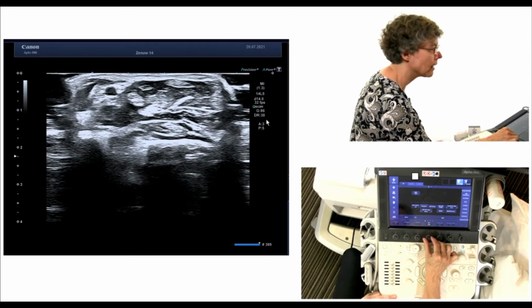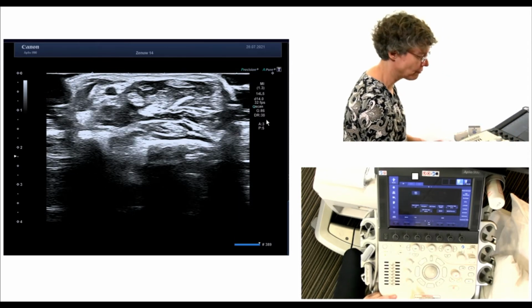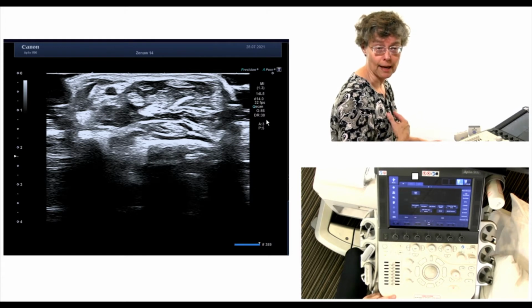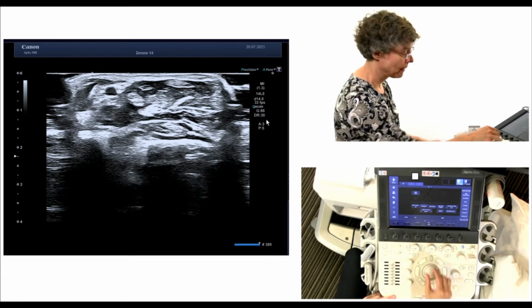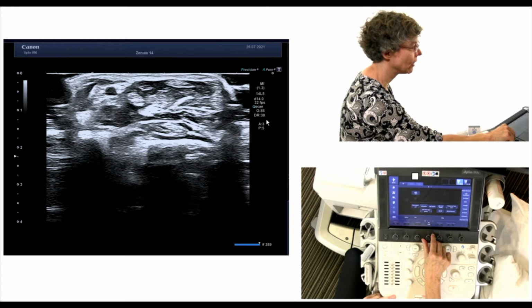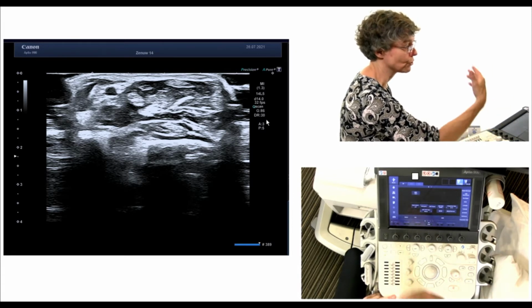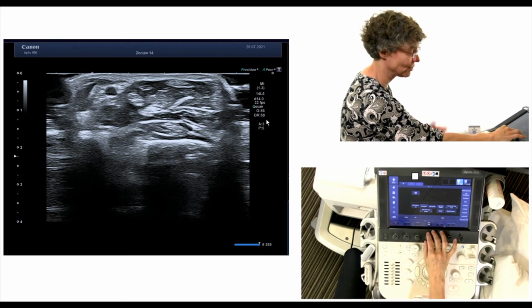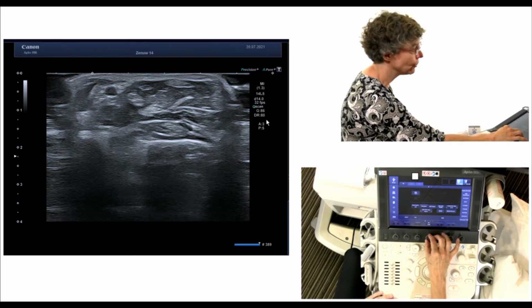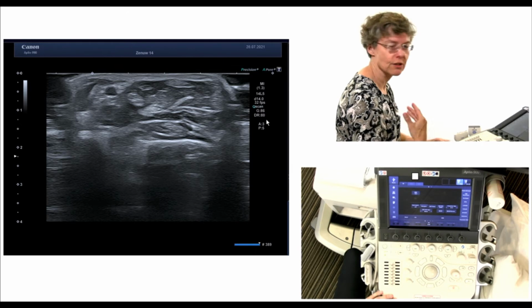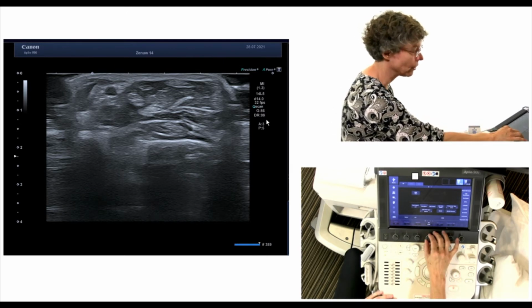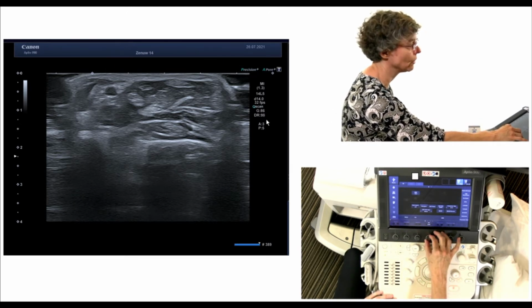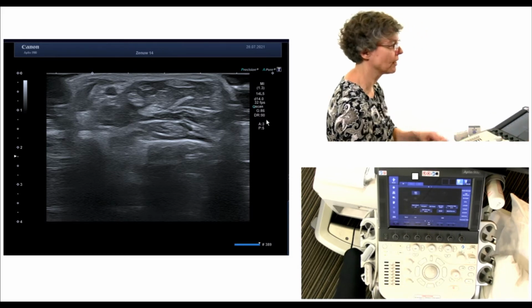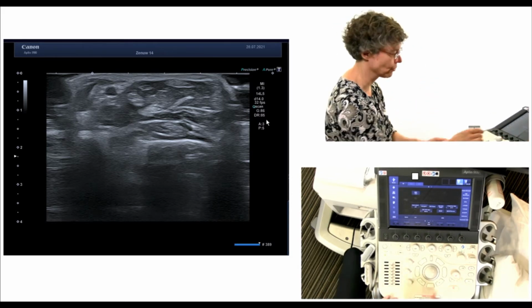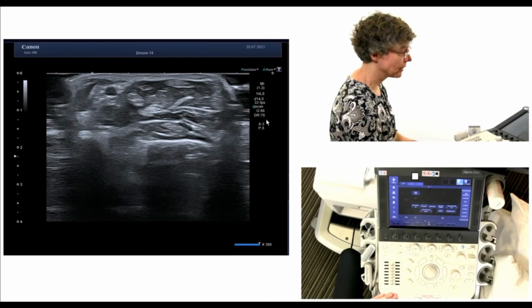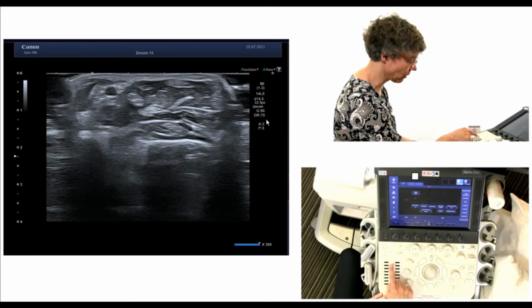And if we turn that down, the image becomes harder, right? So every pixel is sort of forced to choose between am I white or am I black? And if I decrease this a lot, every pixel on the screen will actually make that choice, and you will only have black or white pixels here, which is a very hard image. If I turn the dynamic range up, you see that a lot of grayscale extra levels are shown on the screen. So they are in the signal, but now they're also displaying here. And this is the maximum level, and it's quite soft. You know, all the grayscale tones are there. Now there's something else here in the screen as well, because you see these little toggles here.